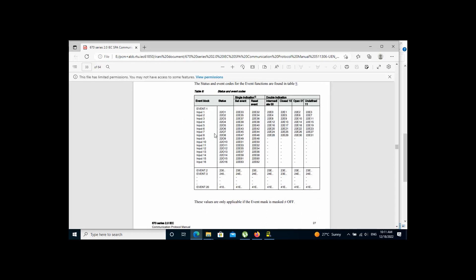This table will show you the addresses of the event. If we look at event 1 — which means event block number 1 — each event block has 16 inputs. The status addresses are 2201, 2202, 2203. This is for event block number 1, which means the channel is 22. 1 represents the number of inputs: 1 for input 1, 2 for input 2, 3 for input 3, 4 for input 4. The channel number for event block number 1 is 22. For the set event — when the signal goes from 0 to 1 — this takes number 33. For the reset event — when the signal goes from 1 to 0 — we take number 32.